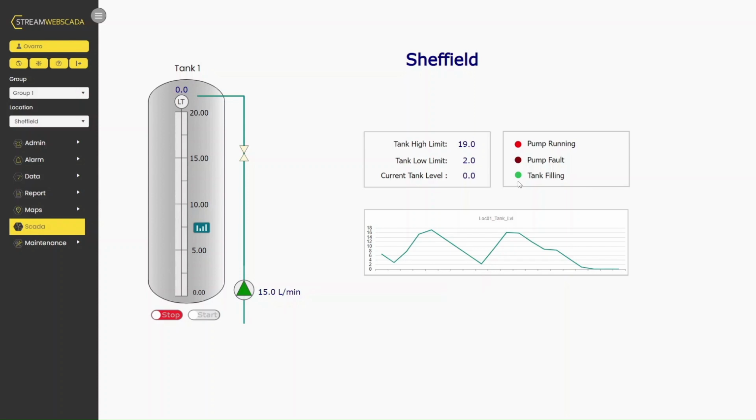So we've got digital contacts, we've got analog values, we've also got a state change. This is 4 different colors, matching the colors we're using on the state display on the map, and state text here. So depending on the state of the site, we get text values. So there's lots of different ways to show the information to your operators so they can see what's going on. And we can see our bar starting to refill here, and we have a trend here. Now, you'll see there's no time at the bottom. This is the last 20 values that we received from site for this particular point. This shows you, is our value rising? Is it falling? What's going on at the particular site?